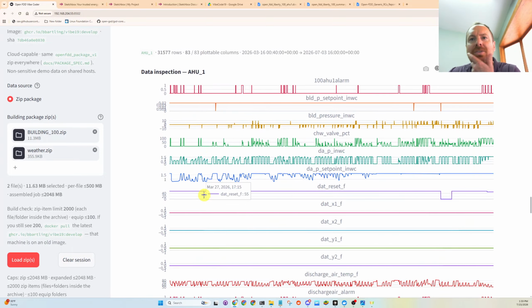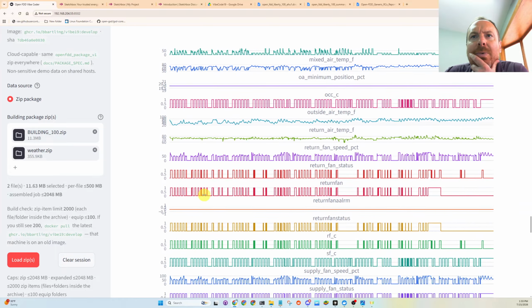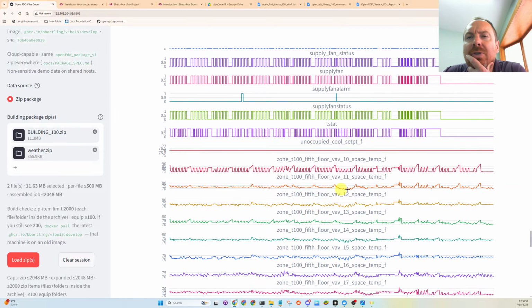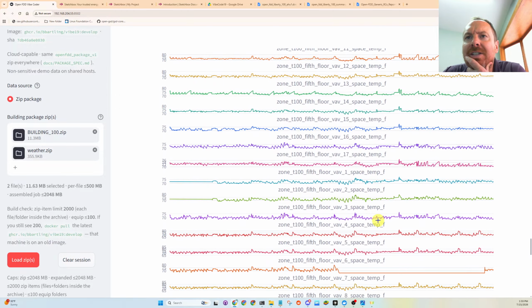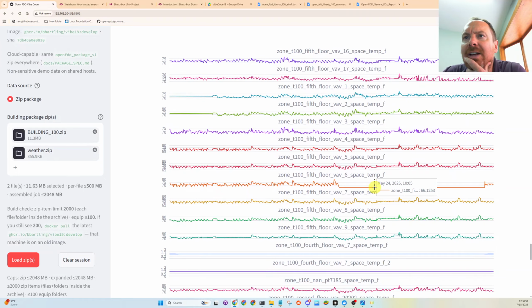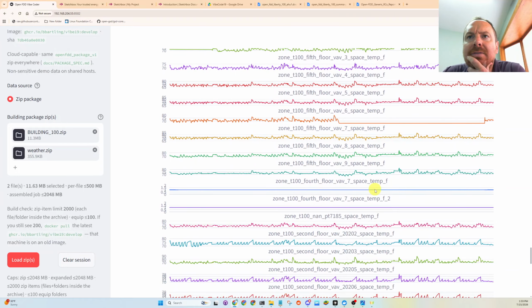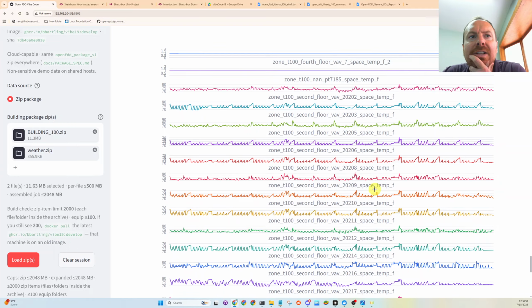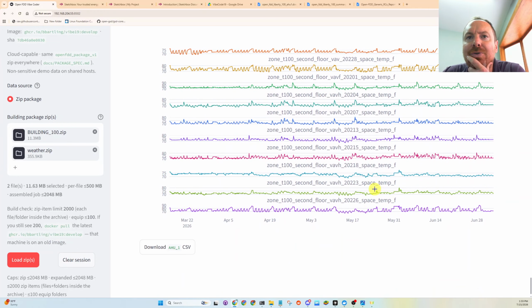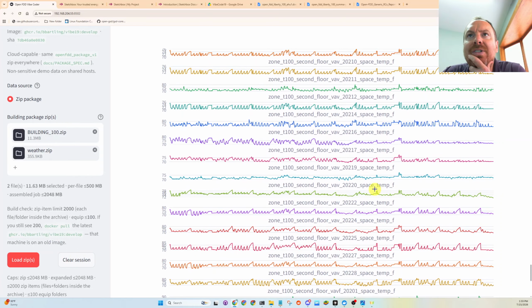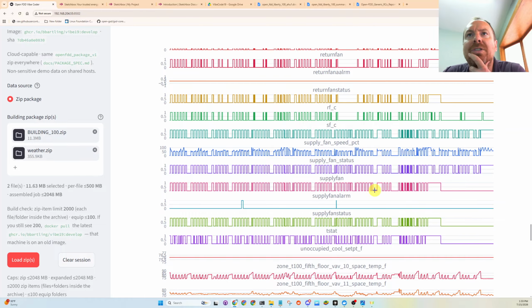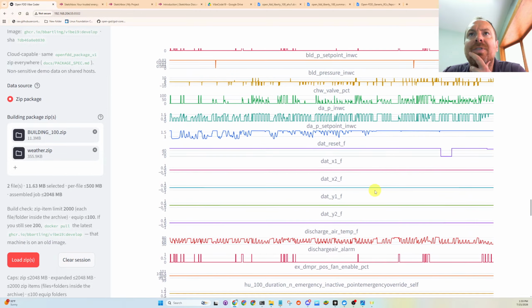Okay, so then this is this raw data. Wow, there's a lot of raw data. So it looks like we do have VAV space temperatures, a lot of flatlined data. So I'm just kind of looking through here. This is a new chart I added for just investigating. Just kind of look once over on this raw data before we feed it into the machine.